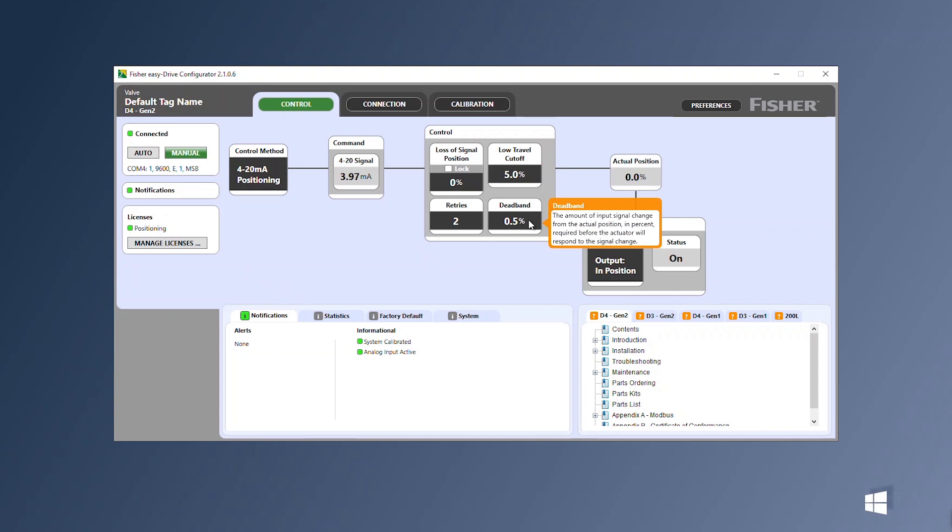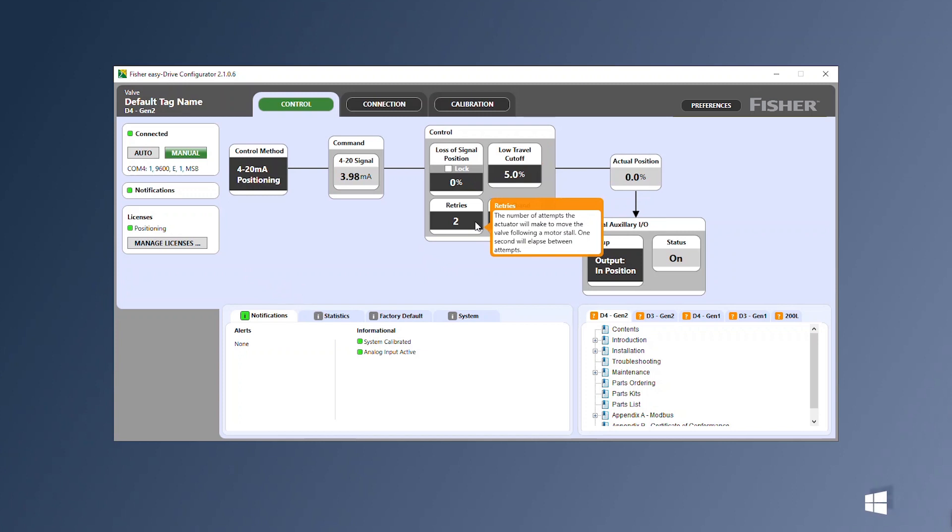The dead band is the minimum change in input signal before a move will occur. Retries determine how many times the valve will attempt to move following a motor stall.